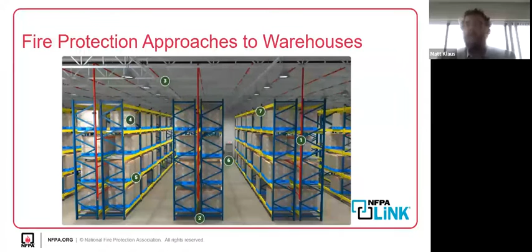Brian talked a little about this, and the title of this is Know Your Hazard. If I've got fertilizer on pallets, a cold storage area, or maybe bulk flammable liquids, the fire protection approach for the building might be designed to limit those to a certain area, maybe an outdoor fenced-in area. If I'm a retail space, I keep all those fertilizers outside. Does my team know what that hazard is, and that a sprinkler system may not be the right mitigation strategy for that potential hazard? That's why we keep them outside, because if something happens, we need natural ventilation as part of our strategy. Knowing that strategy and knowing the hazard will allow you to develop the right fire protection approach and inform your staff and teams the right way.